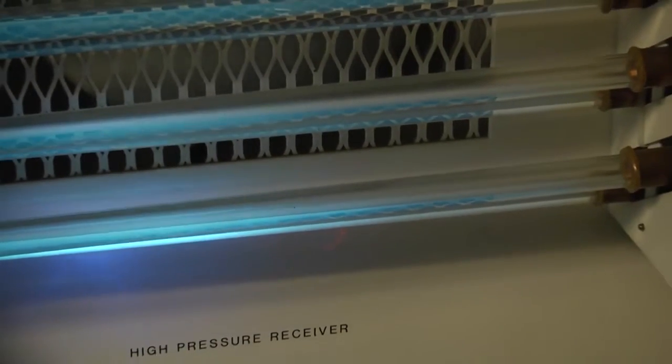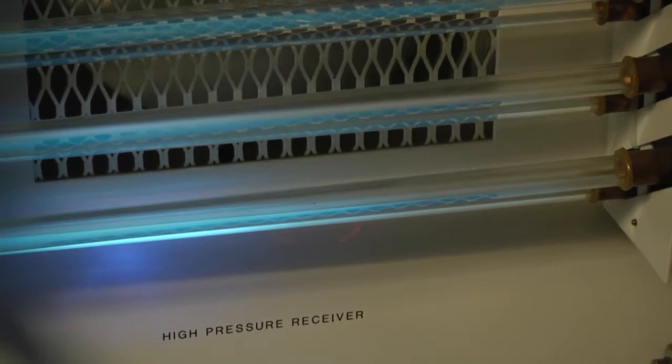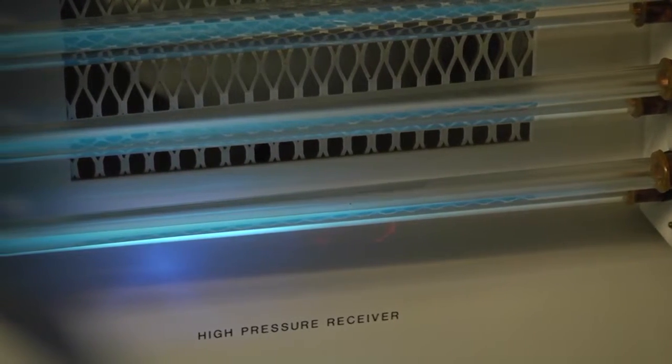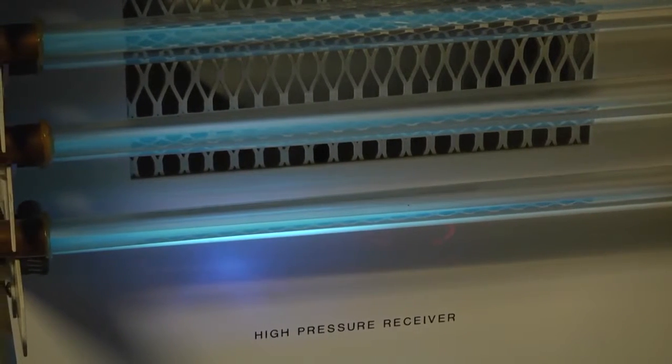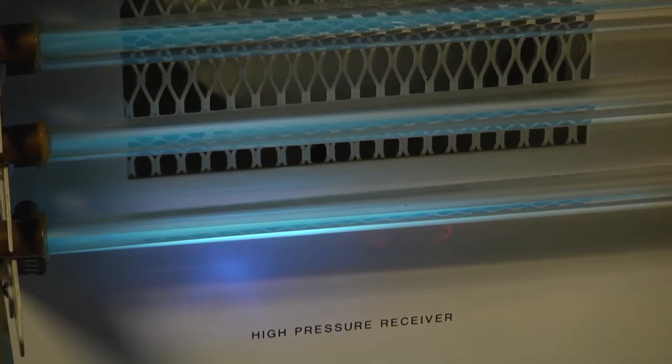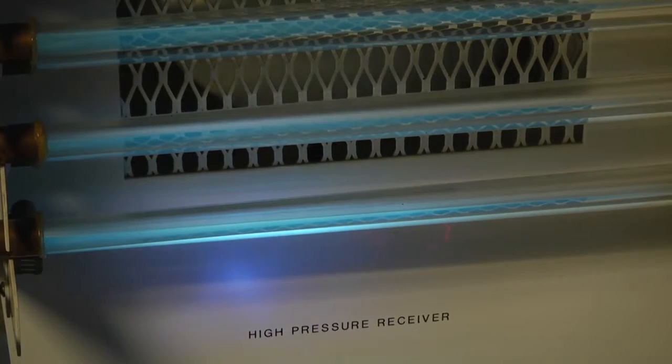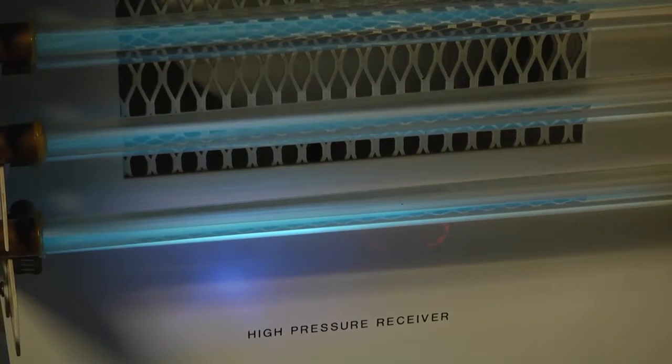We're going to continue to remove heat. And just like we did in the evaporator coil, we're going to continually change the temperature of the refrigerant. Now that it's 100% liquid refrigerant, we're going to continue to drop its temperature. Dropping the temperature of that refrigerant is called subcooling, or dropping it below its condensing point.